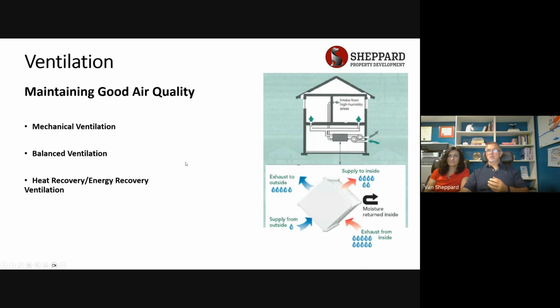So, energy recovery ventilator. It's similar to an HRV. It's the same box. It's the same ductwork. The difference is in the heat exchanger core. In a heat recovery ventilator, moisture gets passed out and dry air comes in. In an energy recovery ventilator, there's some return of moisture to the inside. If you're in a heating environment. If you're in a cooling environment, you're going to reject the moisture to the outside.